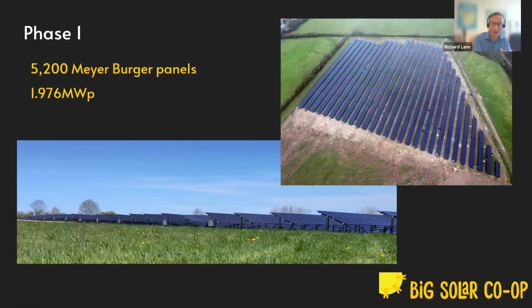So we are currently within our grid limit. The idea is that we have a constrained grid limit, but we are going to overload it. We have a very high AC-DC ratio, partly because we're using second-hand panels, as John said, so we're expecting them to have degraded. In order to get as much juice as possible through that 2 megawatt limit, we're going to have a high overrating on the DC side.